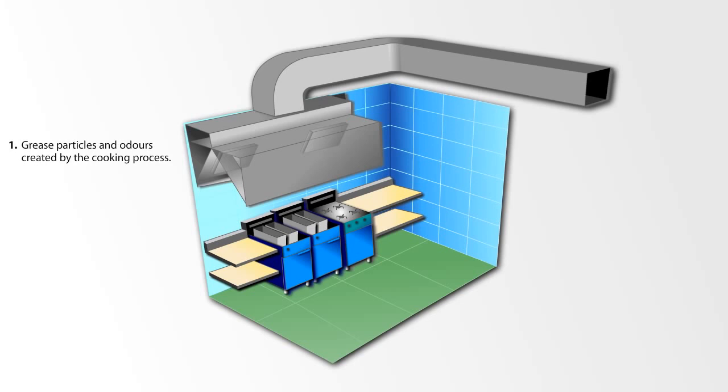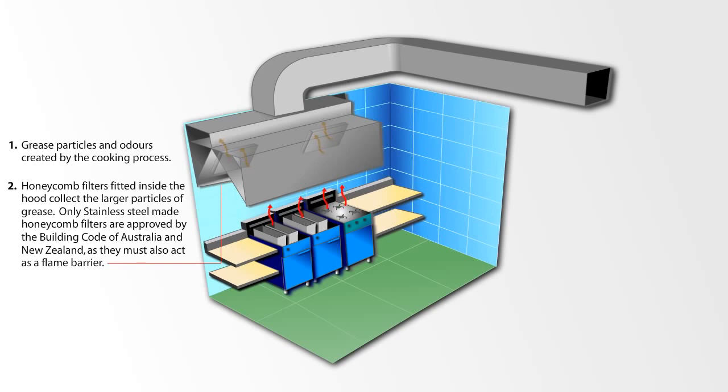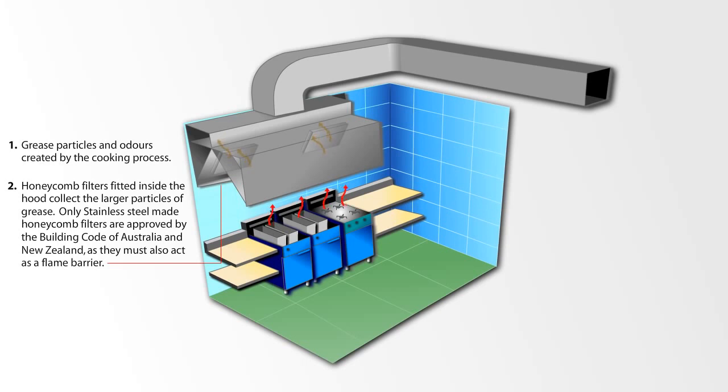Grease particles and odours created by the cooking process. Honeycomb filters fitted inside the hood collect the larger particles of grease. Only stainless steel made honeycomb filters are approved by the Building Code of Australia and New Zealand, as they must also act as a flame barrier.